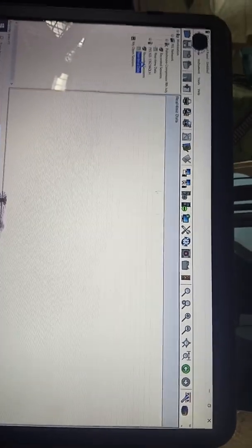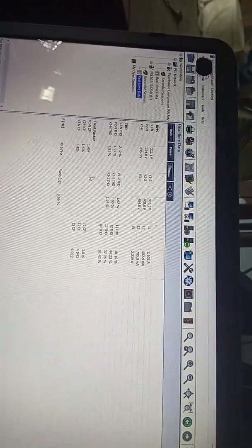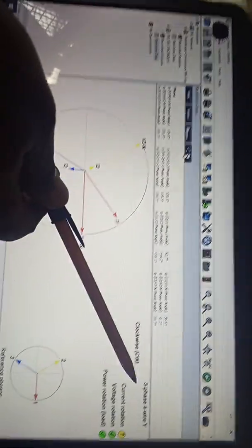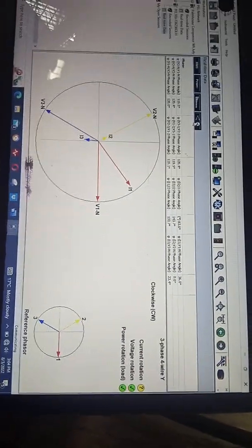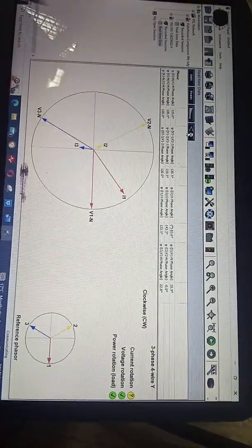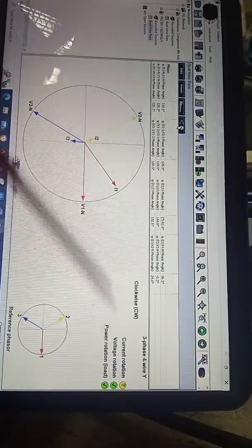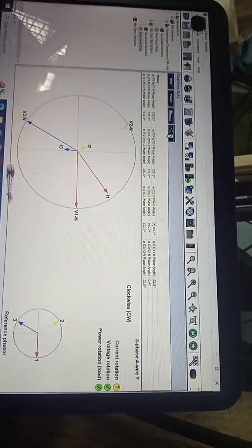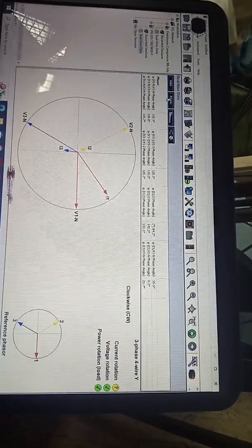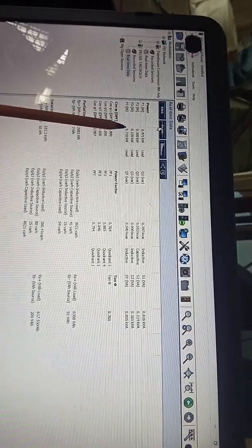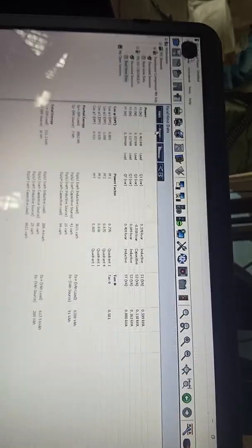We can now come to the real-time data. We are able to see the voltage being supplied and the current. Notice that we have gone down because the machine is off as we are talking. We have the phasor diagram which gives the current rotation, the voltage rotation, and the power rotation, which will be about 120 degrees. The current rotation is giving us a question mark because the machine is not running. Right now line 1 is consuming 0.47 kW and the total is 0.710 kW because this is idle power.